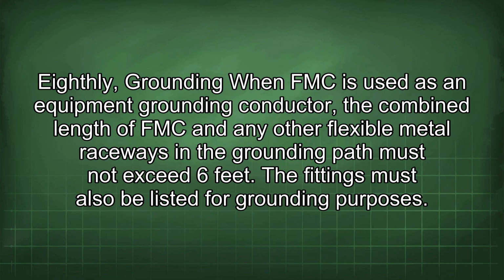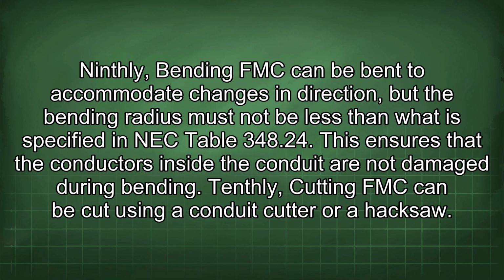Eighthly, grounding. When FMC is used as an equipment grounding conductor, the combined length of FMC and any other flexible metal raceways in the grounding path must not exceed 6 feet. The fittings must also be listed for grounding purposes. Ninthly, bending. FMC can be bent to accommodate changes in direction, but the bending radius must not be less than what is specified in NEC Table 348.24. This ensures that the conductors inside the conduit are not damaged during bending.